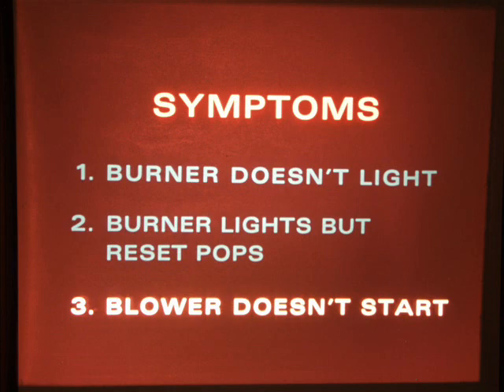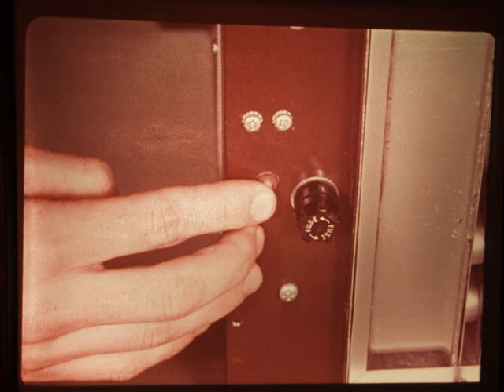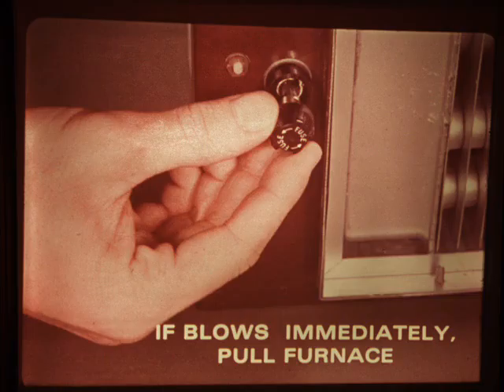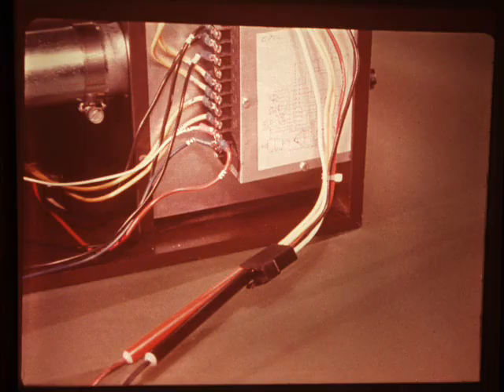The final problem we'll cover is a furnace with a blower that fails to start up when the thermostat calls for heat. Obviously, the first thing to do is press the reset. If the furnace runs, you're all set. If not, check the fuse. It may have blown from a surge of current. If necessary, install a new fuse. If the new fuse blows immediately, pull the furnace to test the control box, which we'll cover in a minute.